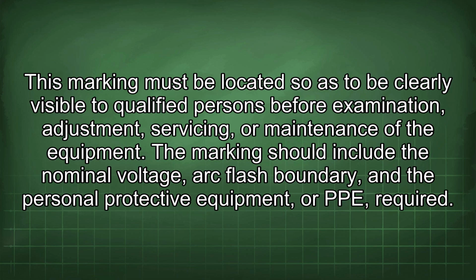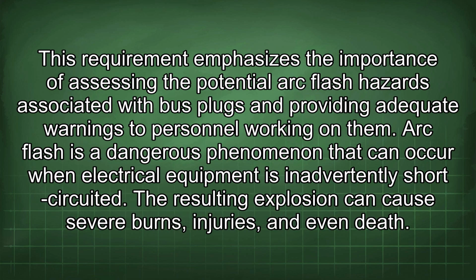This marking must be located so as to be clearly visible to qualified persons before examination, adjustment, servicing, or maintenance of the equipment. The marking should include the nominal voltage, arc flash boundary, and the personal protective equipment, or PPE, required. This requirement emphasizes the importance of assessing the potential arc flash hazards associated with bus plugs and providing adequate warnings to personnel working on them.